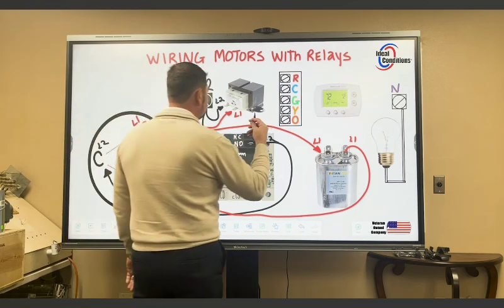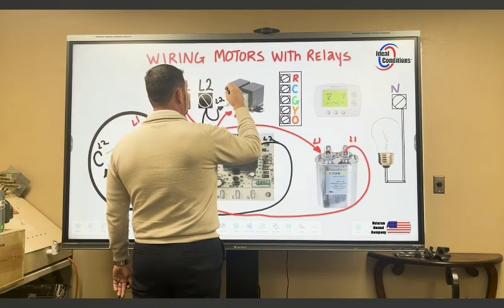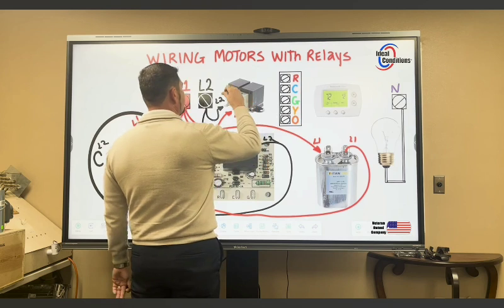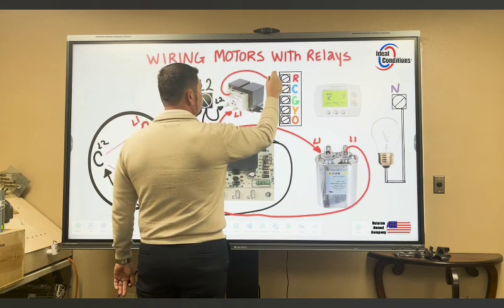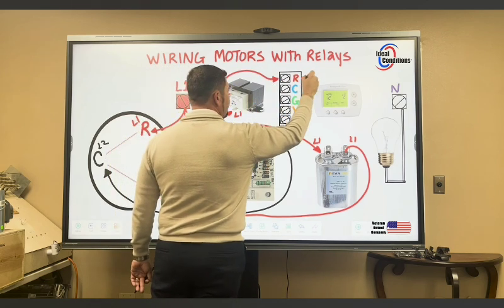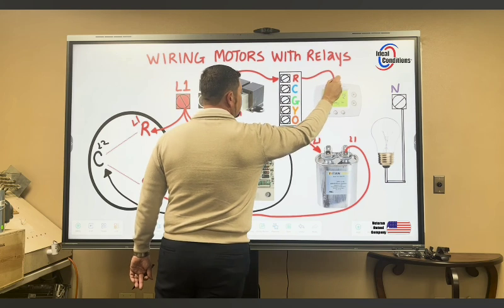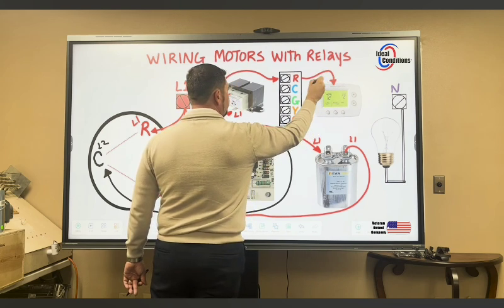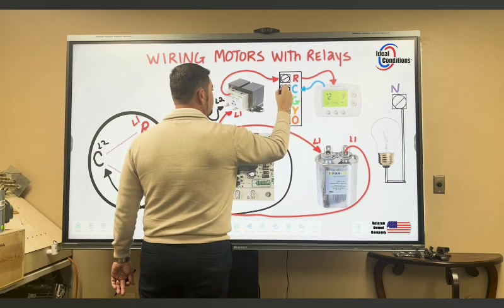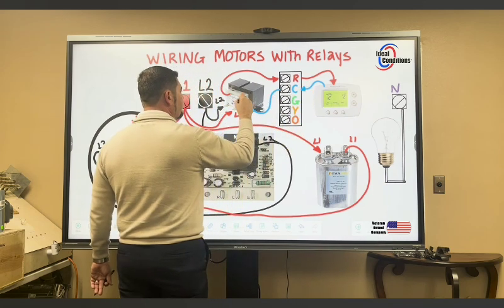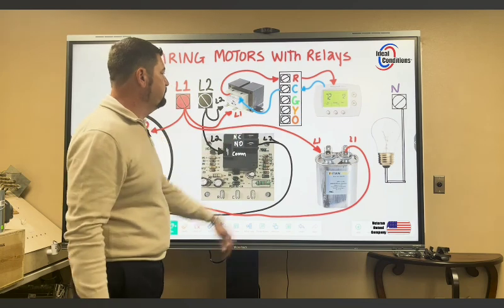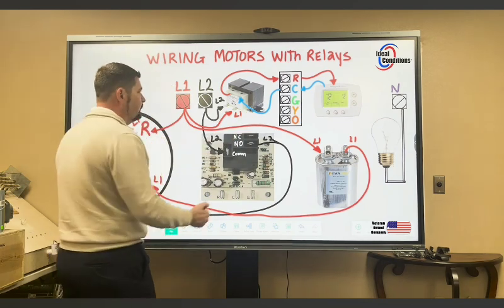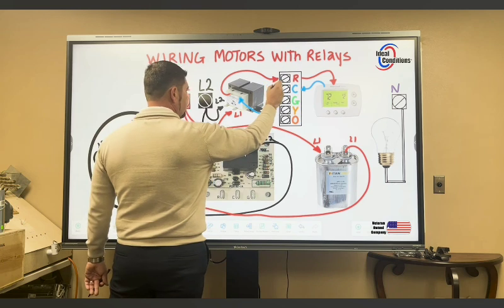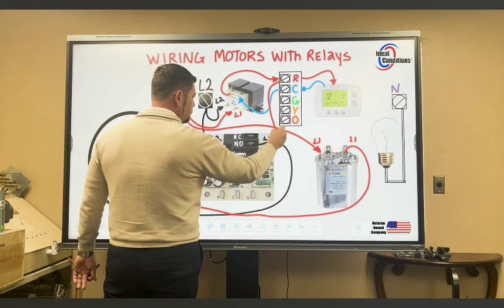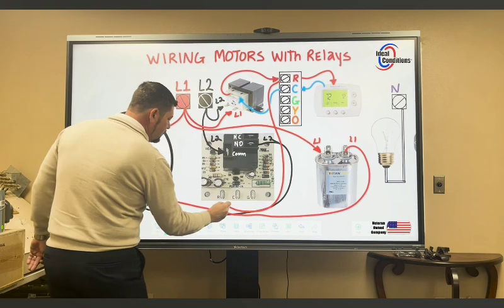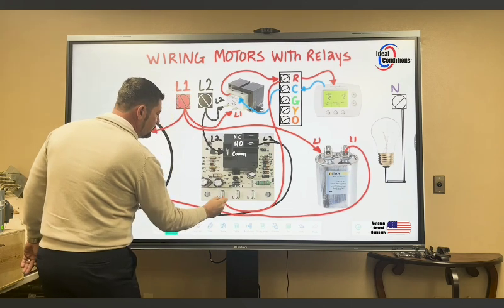We're going to go ahead and run 24 volts over to our terminal block, out of that, over to our thermostat, out of the thermostat, back to our transformer. So we have a path on the low voltage side. Now we'll have a display. We're also going to go ahead and wire up R and C on the blower control board.